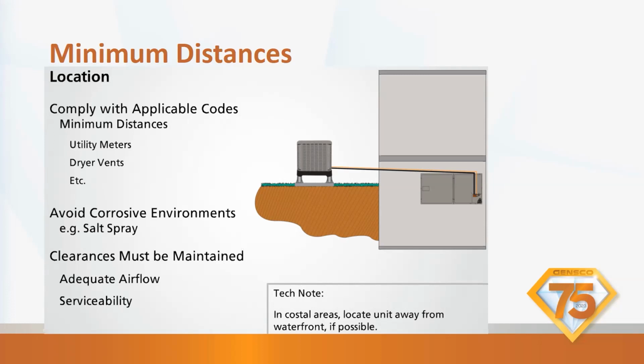And what was happening was the coil was actually defrosting. It was the metal screen on the outside of the coil that would not defrost, because you can only defrost the coil, because that's the only spot that gets hot. Okay. So all of the ice that's forming on the outside of the unit was not being defrosted, causing the unit to have issues. So those are the kinds of things we need to look at when we're installing it. Just look around, look at the area where you're going to be putting it, and be careful where you're putting the stuff. In a coastal area, put it on the opposite side from the waterfront. Try to keep the water spray off as much as we can.